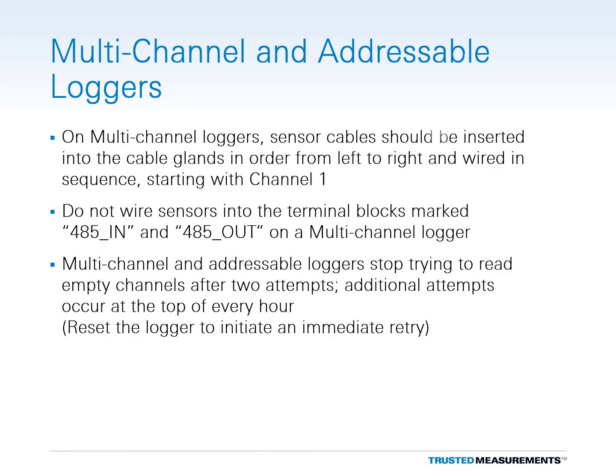For multi-channel loggers, sensor cables should be wired into the channels in sequence from left to right, starting with channel 1. Wire sensors into the terminal blocks marked VW only. Do not wire sensors into the blocks marked 485 in or 485 out.